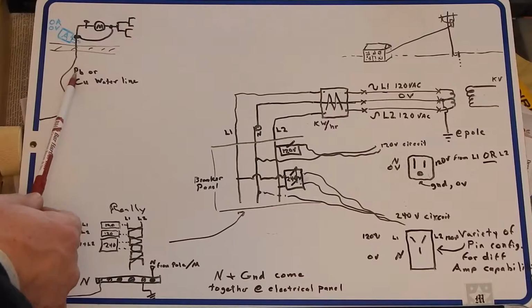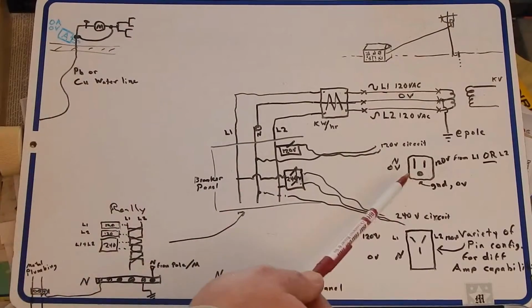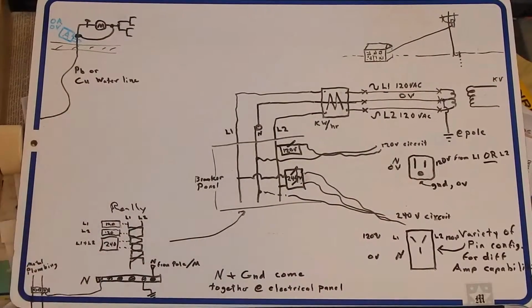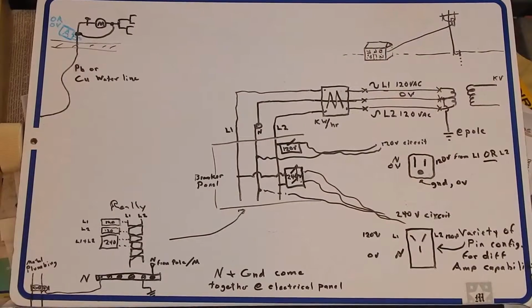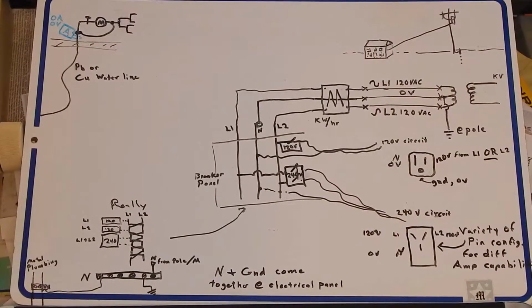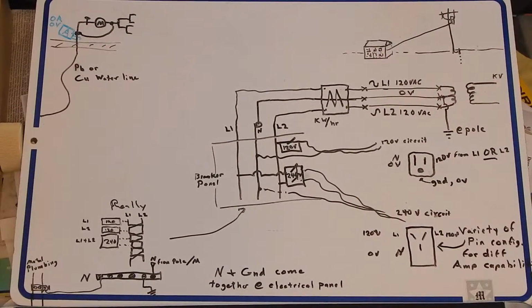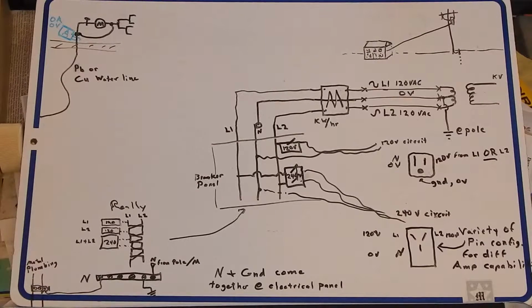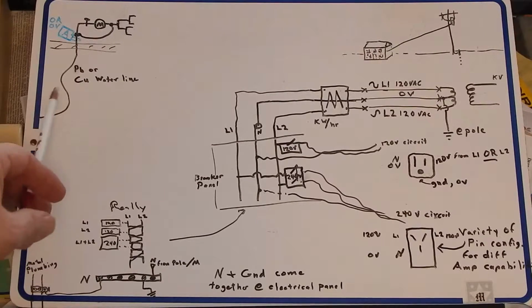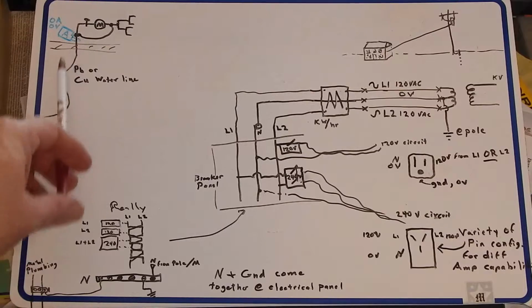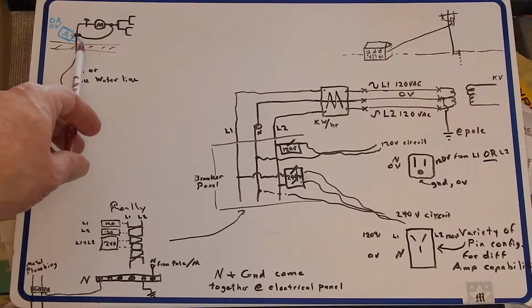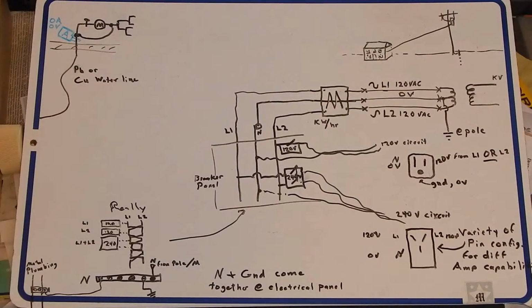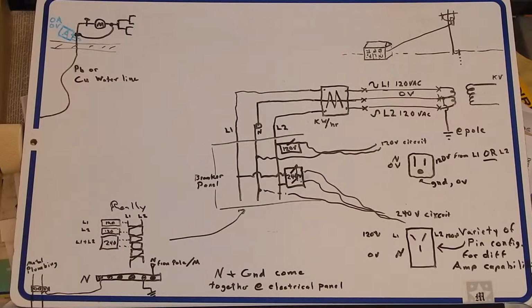Especially if you've got an old lead line and this condition develops, potentially you could be disturbing that oxide layer in your pipe, if you're heating that pipe up. And lead isn't a great conductor, so it will heat up a little bit. That is not a situation you want happening. So, especially if you've got a lead line, you definitely want 0 amps. And any house that's from the 50s or earlier probably has a lead line coming into it.